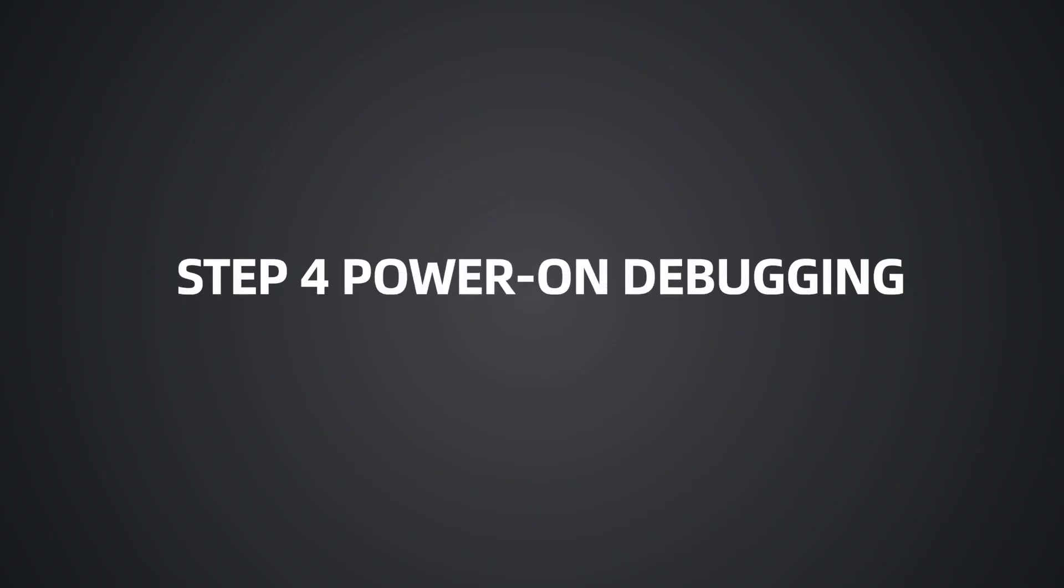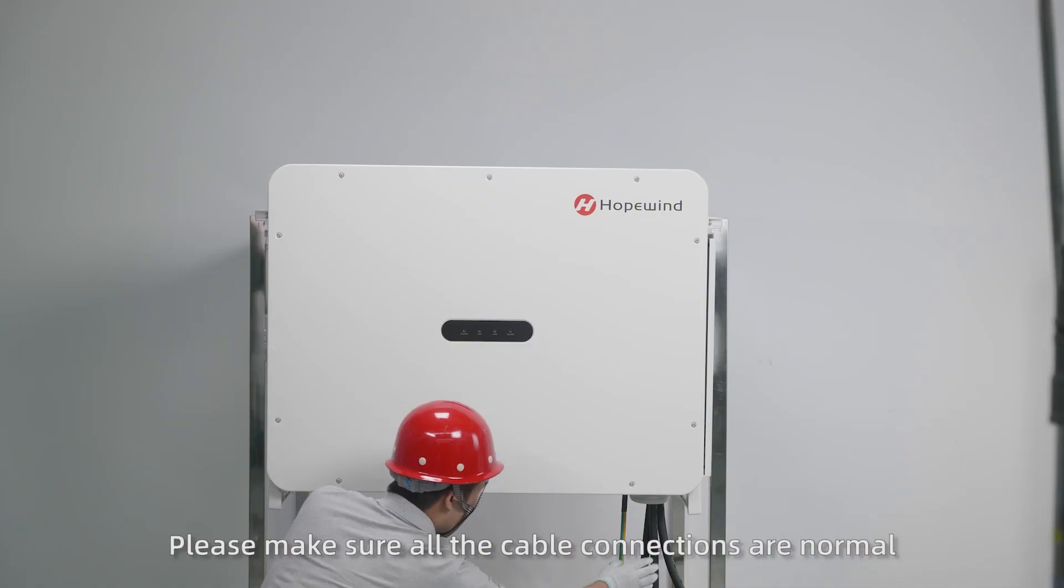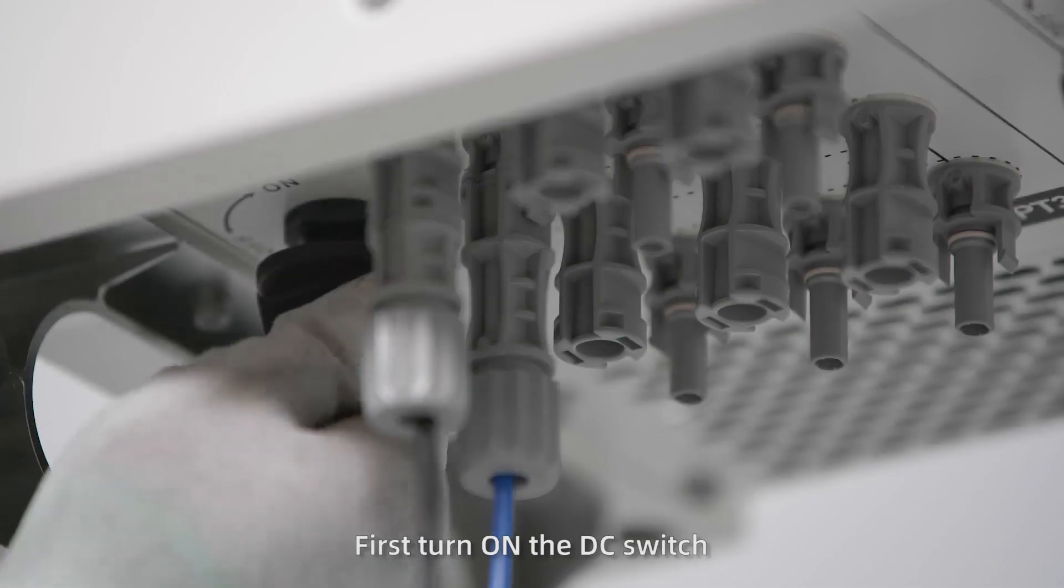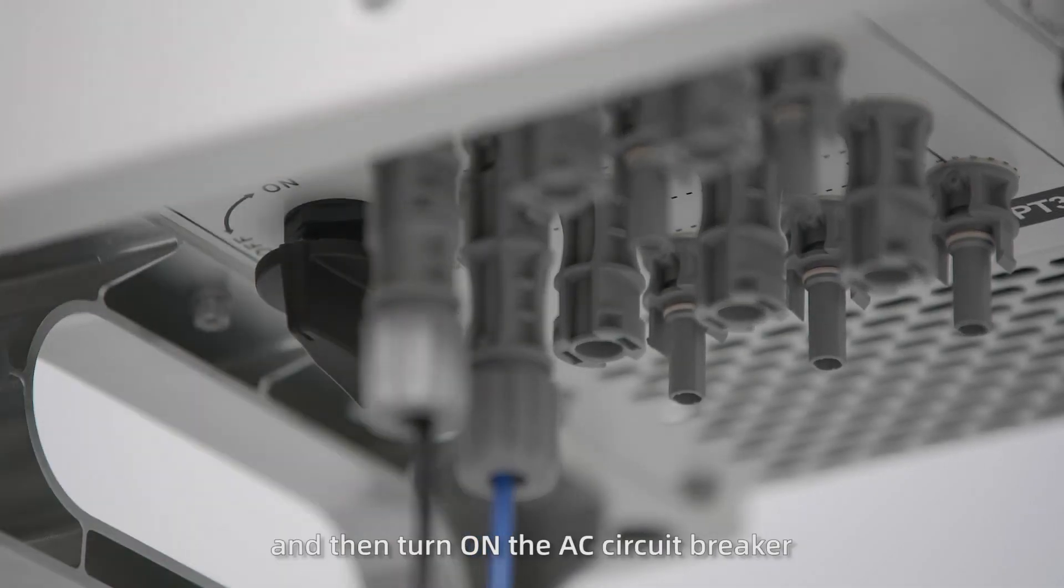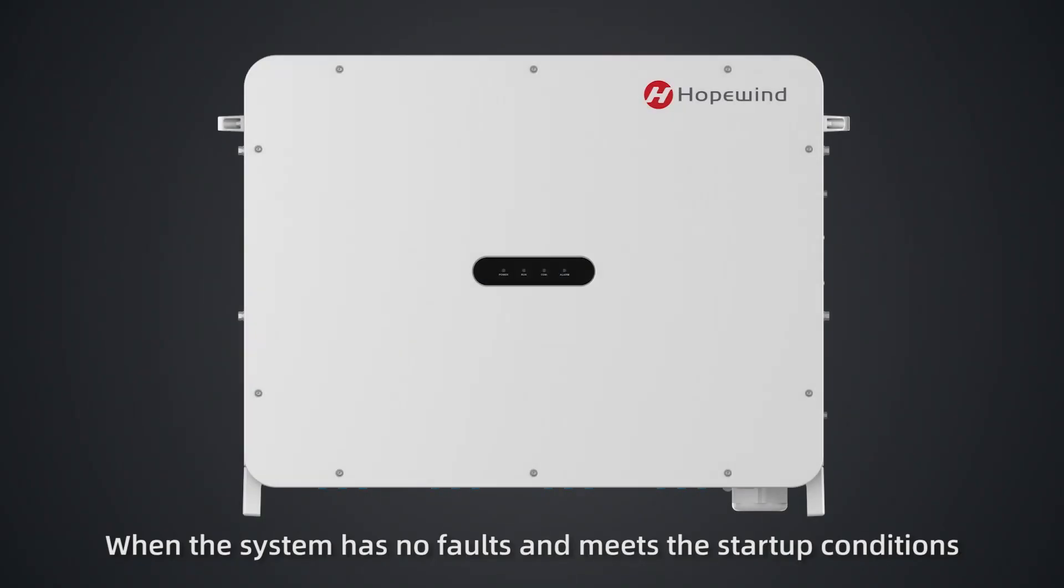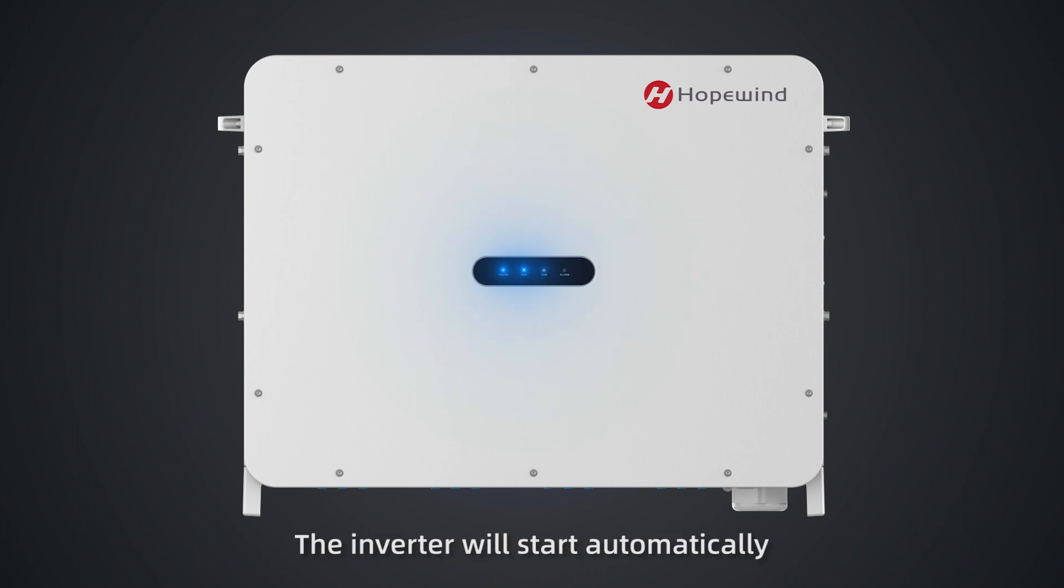Step 4: Power on debugging. Please make sure all the cable connections are normal and stable before power on debugging. First turn on the DC switch, and then turn on the AC circuit breaker. When the system has no faults and meets the startup conditions, the inverter will start automatically.